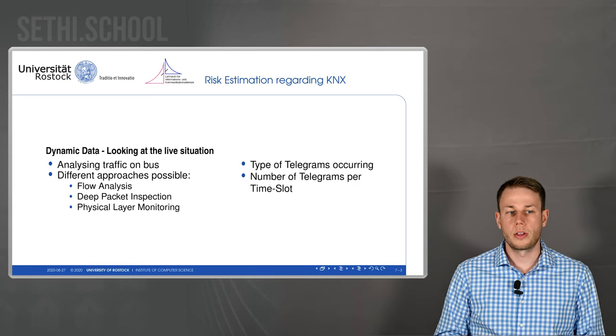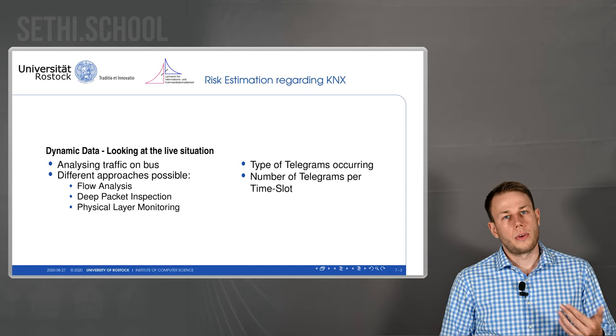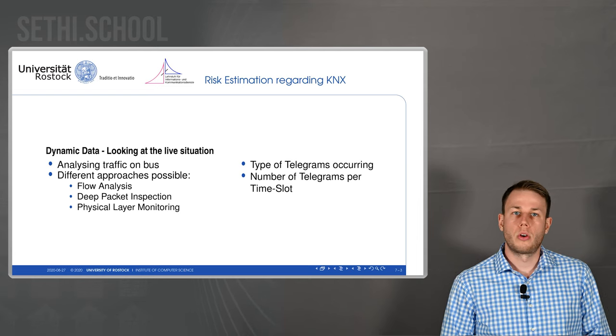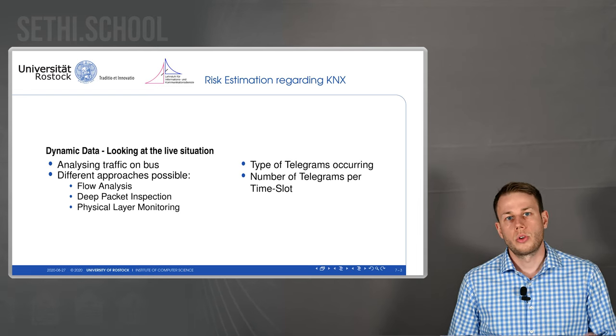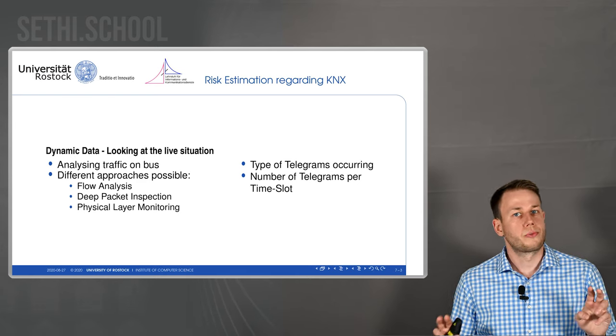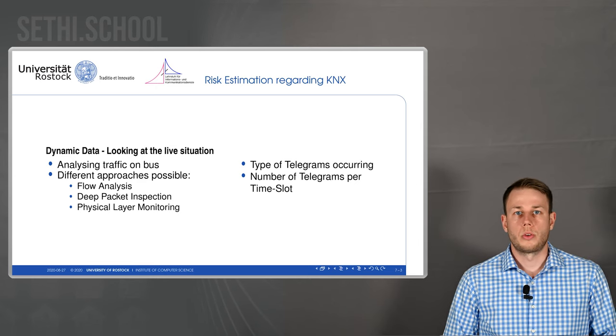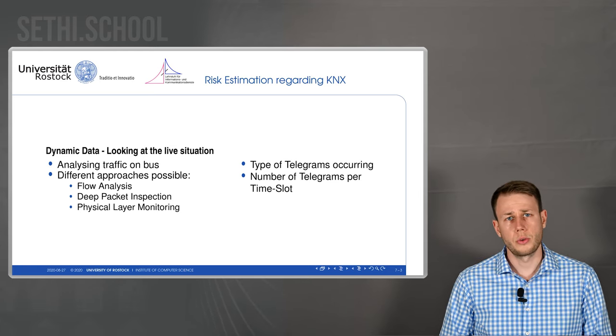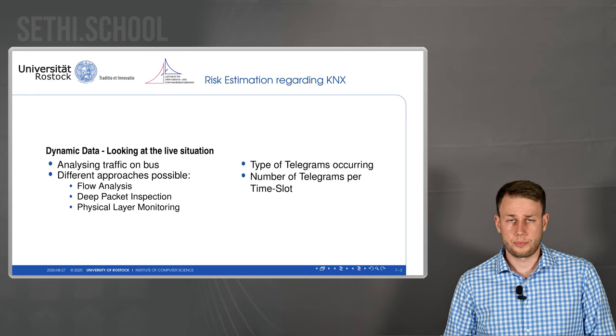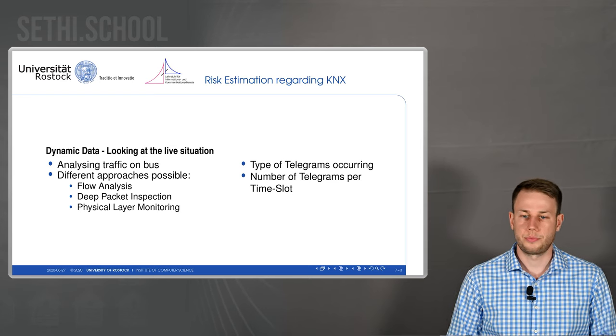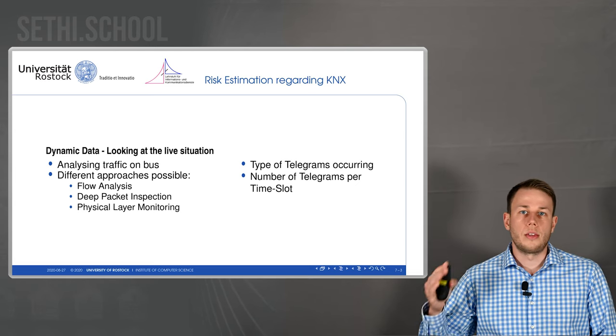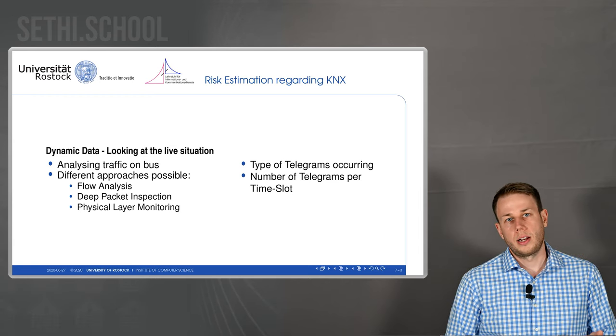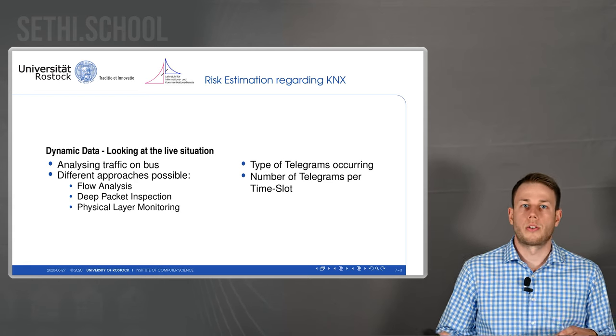Dynamic data is about analyzing the live situation in a network — analyzing the traffic on the bus. There are different approaches: you can do a flow analysis looking only at statistical values such as who is talking to whom and how much data they are transmitting. You can use deep packet inspection, where you look at the actual payload of the telegrams. And you can do physical layer monitoring, where you look if new devices have been attached to the wire but are not talking KNX — examining even below the KNX protocol at the physical level.